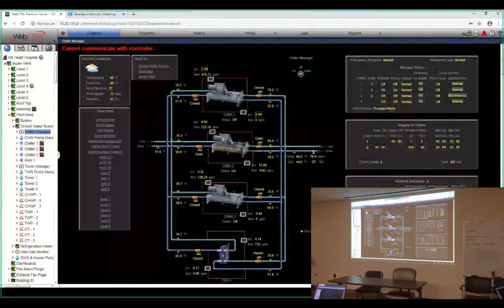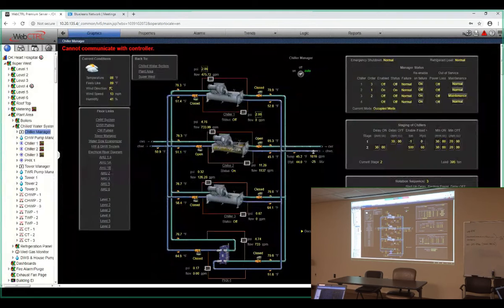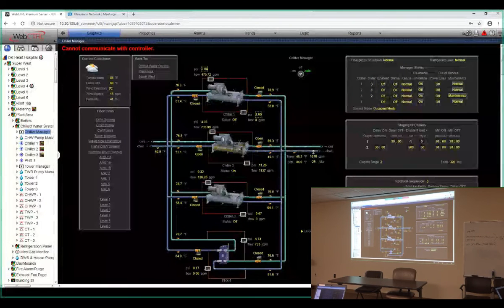Aren't they 500-ton machines? Yeah, but I've seen this get up to 540 when I was running it by itself. So the load I'm basing on the supply and return temp and the flow. Okay. So it is a calculated load. Got it. It's not from integration. There is some secondary staging. If we get 10 degrees out of set point on our chill water, it will also stage one up.